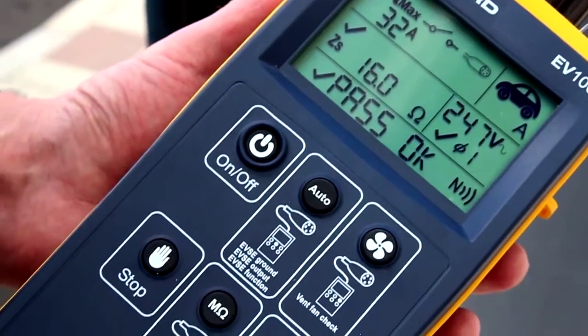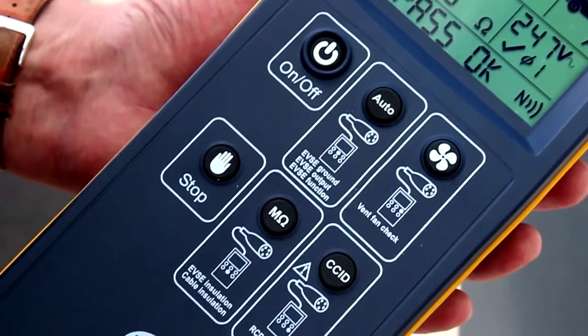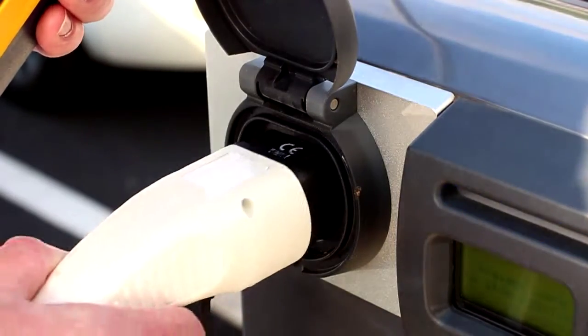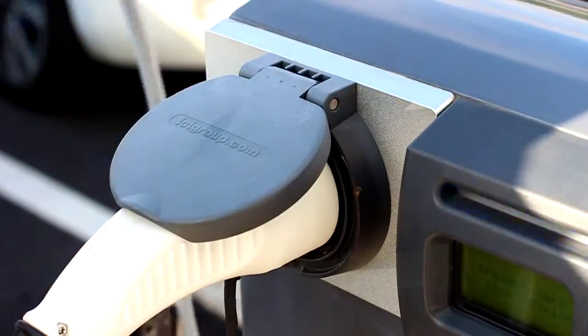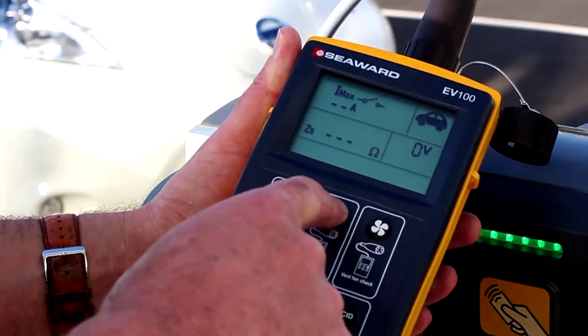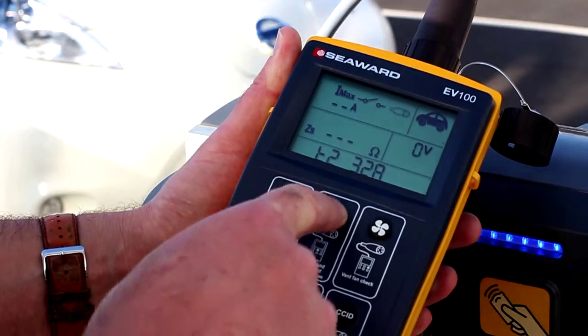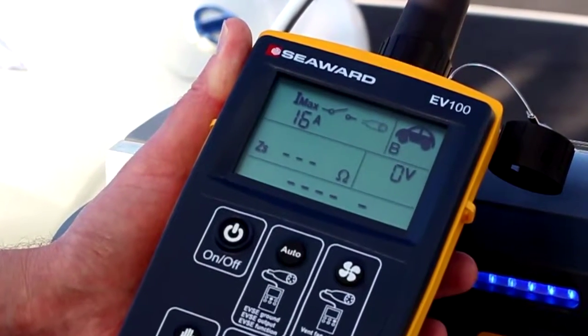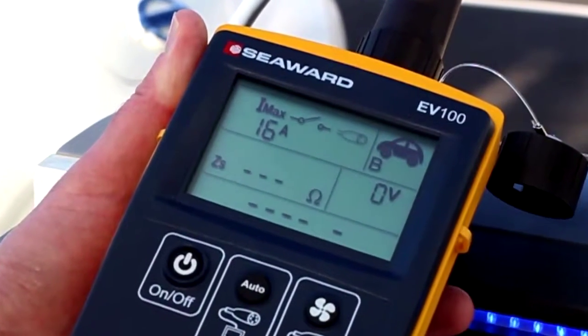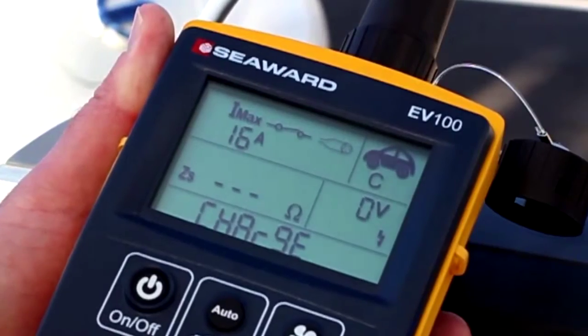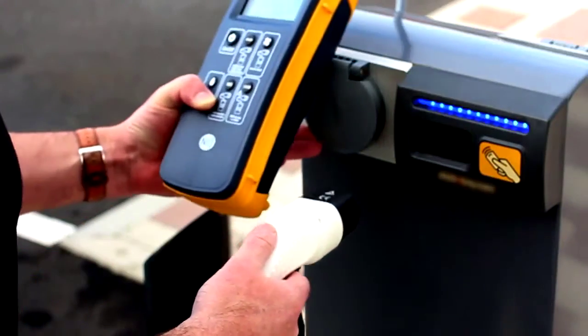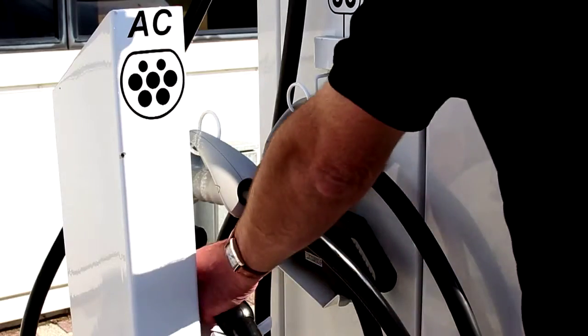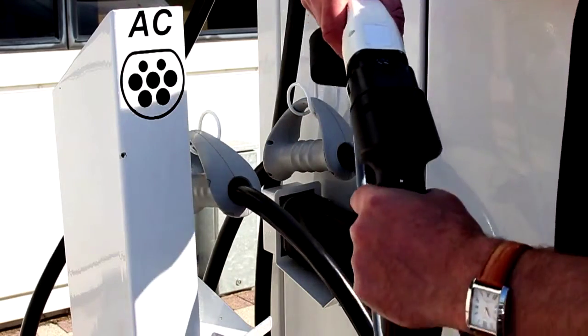The EV100 and EV110 EVSE test and diagnostic tools from Seaward are designed to quickly and efficiently verify that all types of AC electric vehicle supply equipment are operating correctly and safely, both at the time of installation and as part of an ongoing periodic inspection. This instructional video guides you through how to use the EV tester for different test functions. The following tests can be conducted on AC EVSE with a Type 1 or Type 2 socket or one with a tethered cable using the special test adapters.